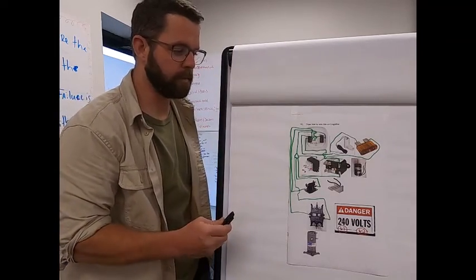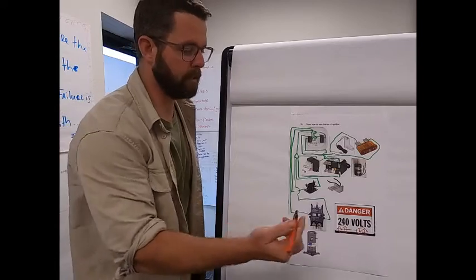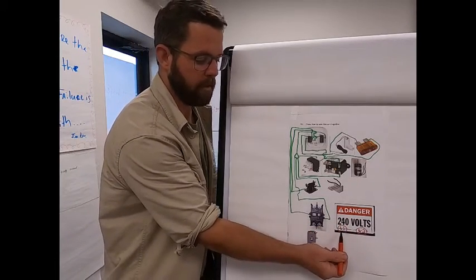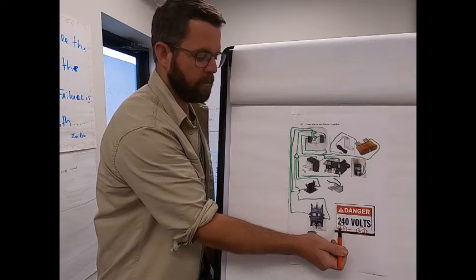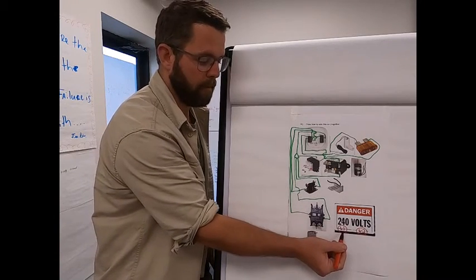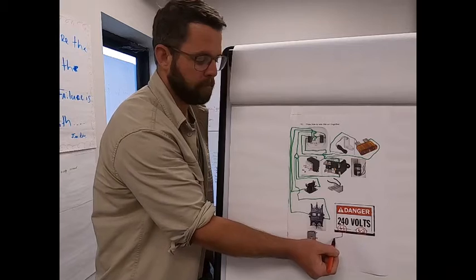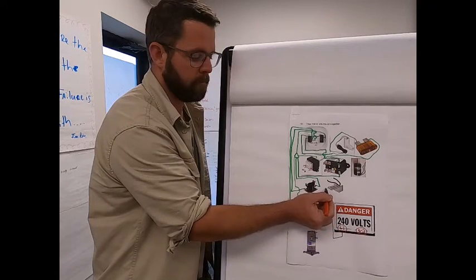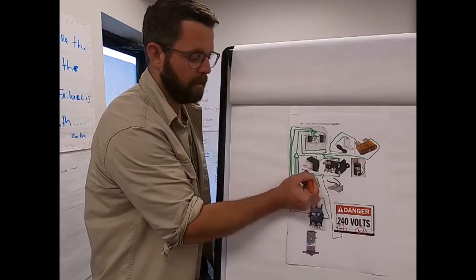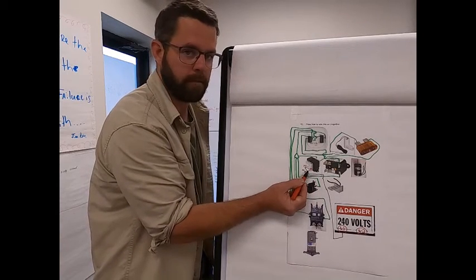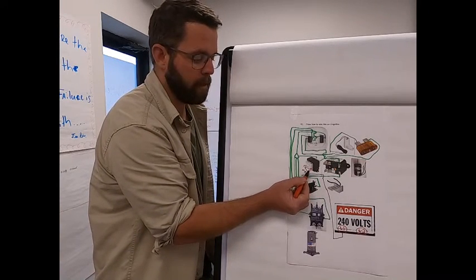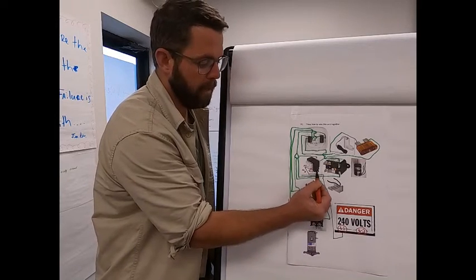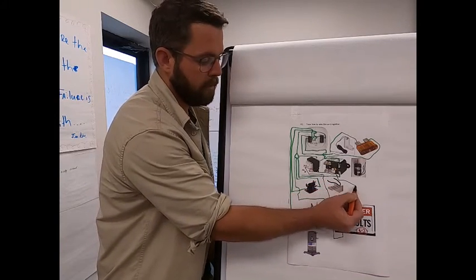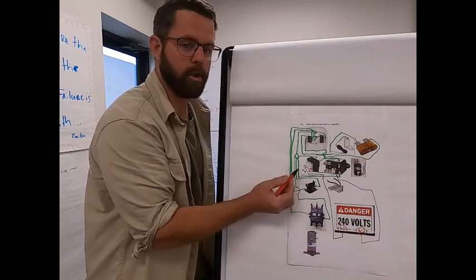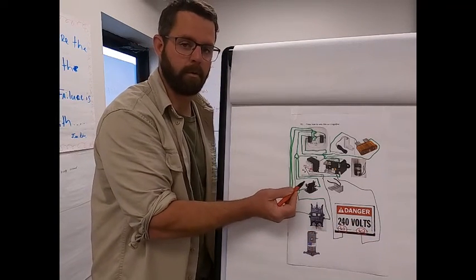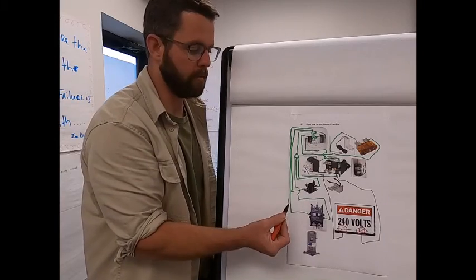To connect high voltage, it is mostly simple. High voltage is listed here, L1 and L2. The first thing that needs to happen is our transformer needs to be powered. So L1 will go to one side of the primary voltage. The other side of the primary voltage will be L2. Now our transformer is powered and can convert 240 volts down to 24.